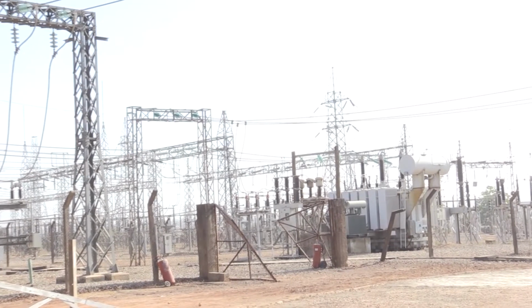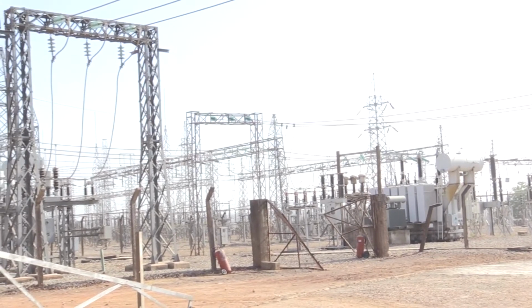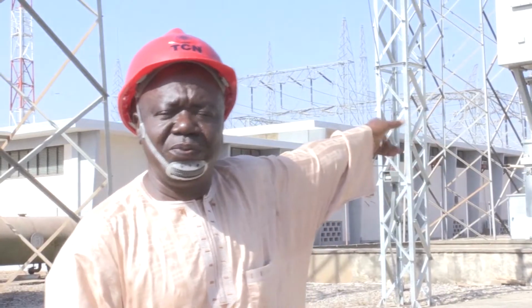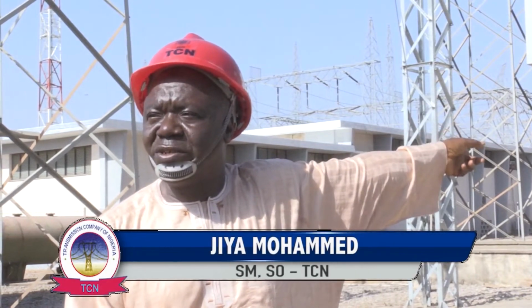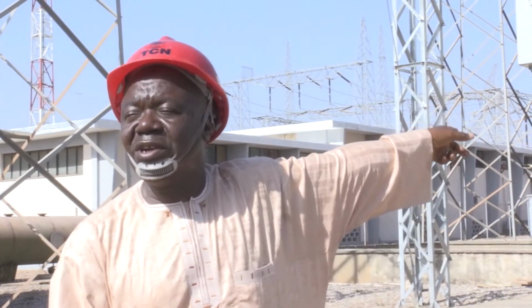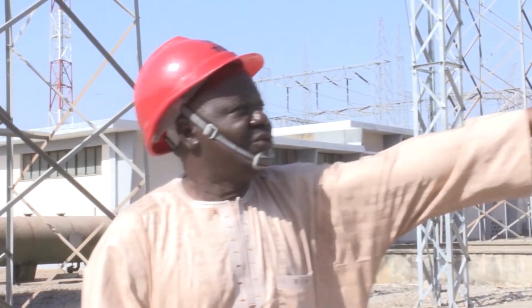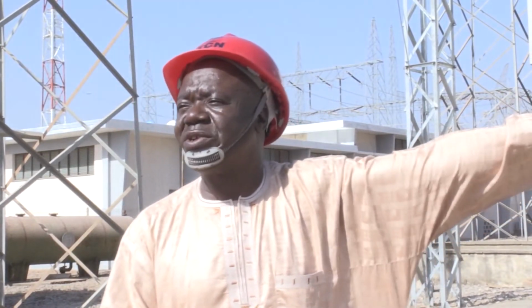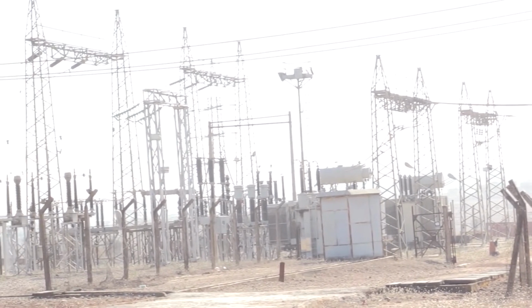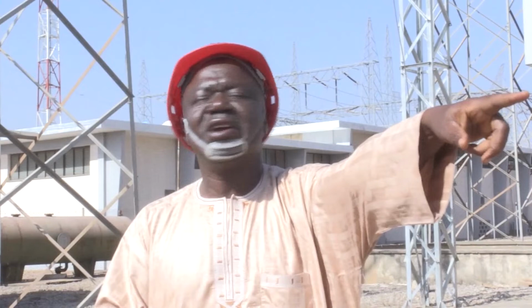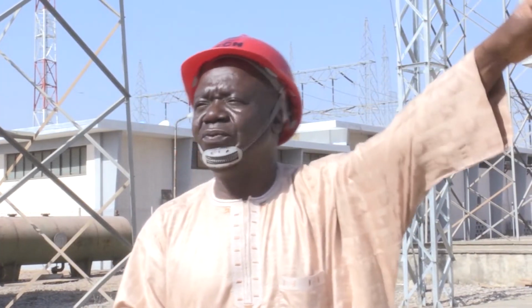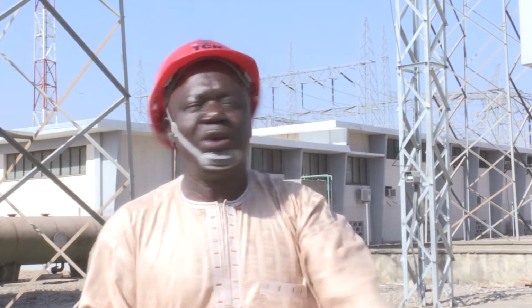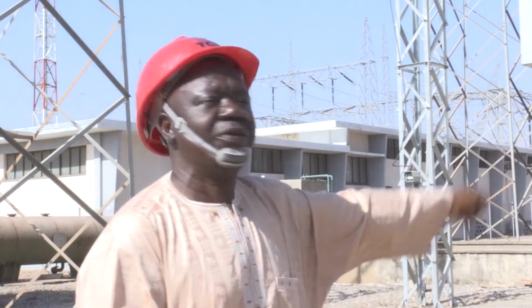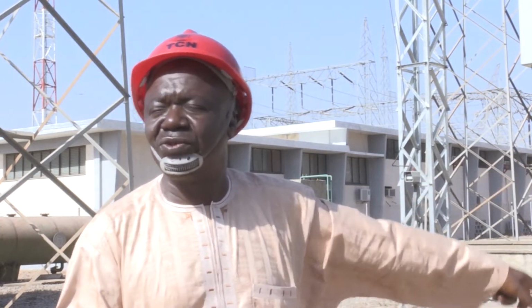Actually, there's improvement. There's improvement because this one now can load up to 100 megawatt, 120 megawatt. That is the maximum load it can carry. This other two can carry 120 megawatt, equivalent to 240 megawatt, as against 60 MVA that can only carry 48 megawatt. This other one 48 megawatt, making 96 megawatt. But these two transformers that you can see can carry 240 megawatt to the consumers.